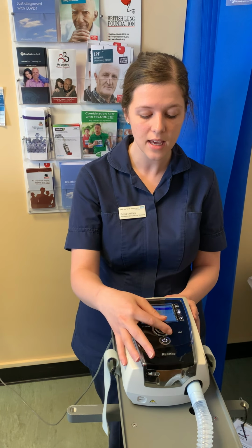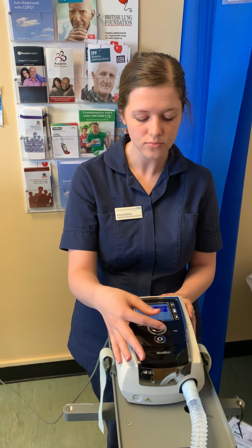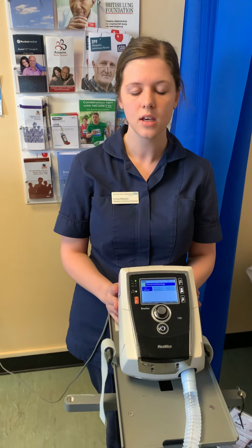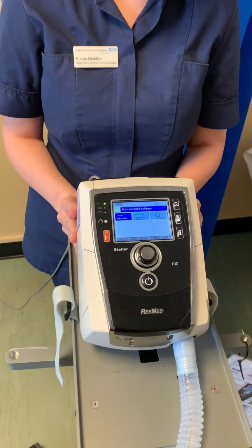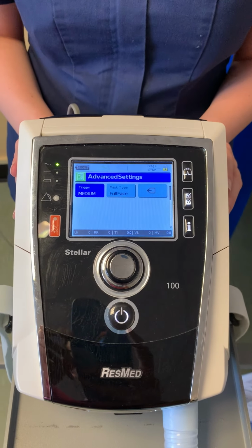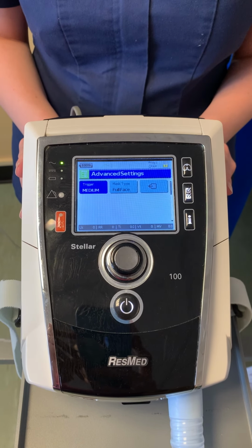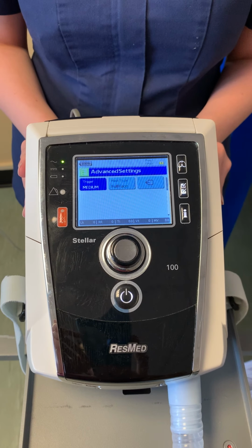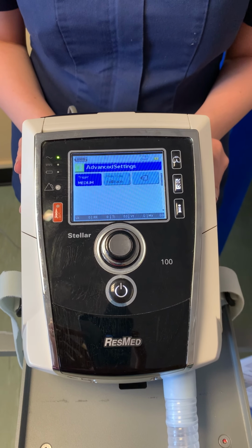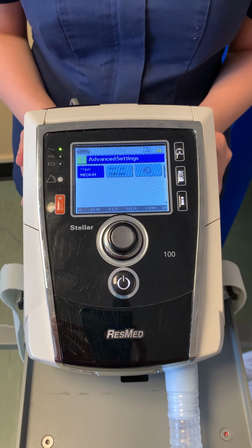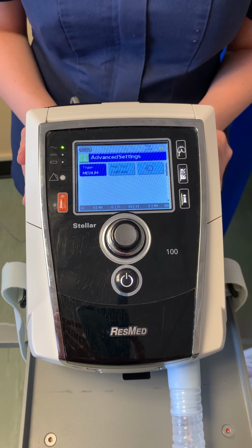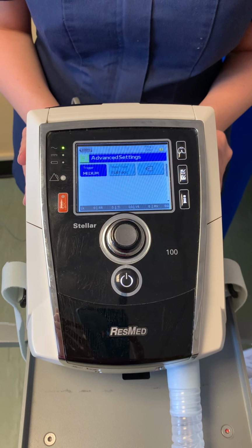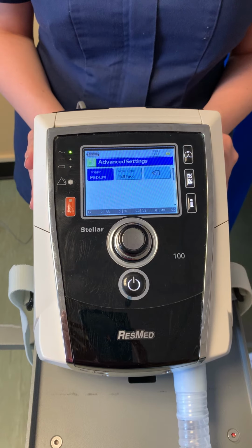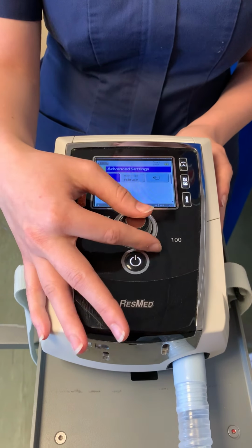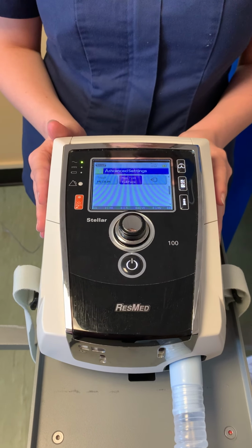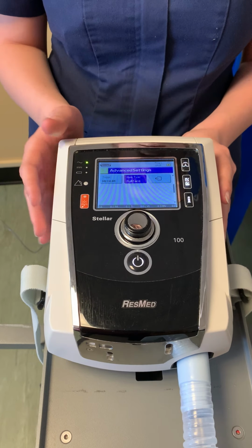The next setting is advanced settings, which really aren't advanced. We have our triggers. The trigger is basically letting the machine know when the patient is inspiring and expiring, so it can understand when to put a backup rate in. It's not really needed for CPAP, however, it's still there. So please just set it at medium unless a respiratory consultant or registrar says otherwise. The next thing is the face mask, which we've already set on the front screen, so we don't need to change it.